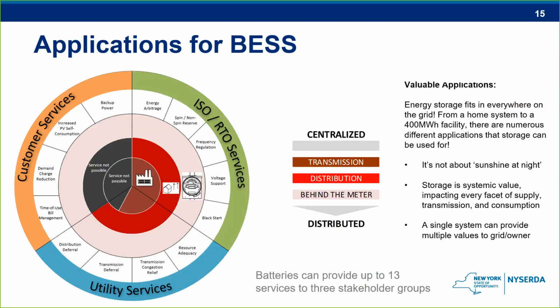So a little bit more detail on why we're even doing this. Most people are familiar with storage as a backup system in the event of a power failure, and that is certainly one usage, but it also has a ton of other relatively largely untapped potential to do things like reduce peak load, provide frequency regulation to protect critical equipment, and probably most importantly for our purposes, make it feasible for the grid to accommodate all the new renewable energy that's coming online. Like I said before, we all know that solar and wind are intermittent power supplies, not always generating electricity when we need it, so storage can help solve that problem.